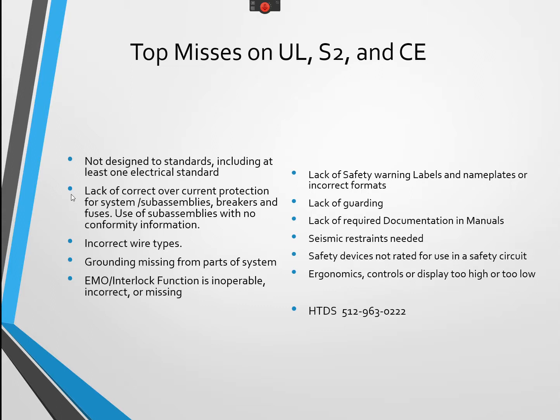Now, a subset of that is lack of overcurrent protection for system subassemblies. This is a big one that people miss, and it really causes a lot of extra time in equipment builds. For example, just recently we had a customer who didn't have overcurrent protection on the primary and secondary of a transformer. They had to go back in and add that, and that's a pretty big effort, especially when you're planning on shipping the equipment within that same month.